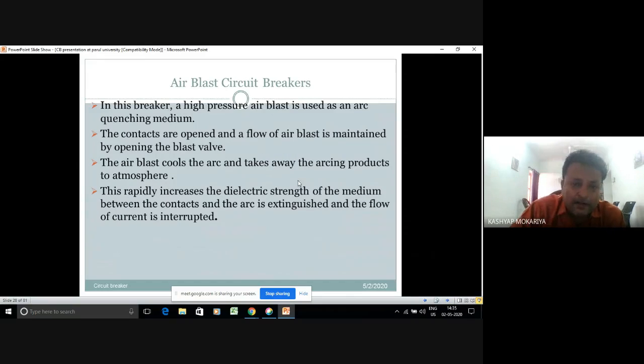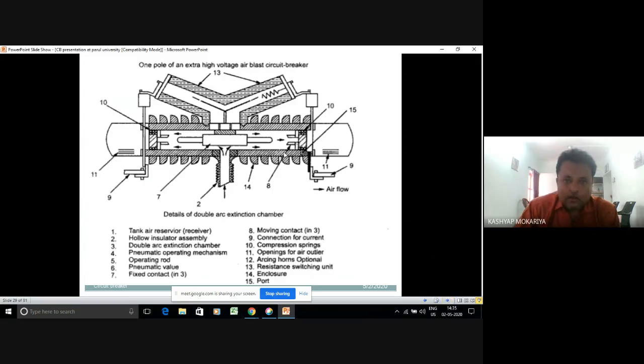Air blast circuit breaker. In this breaker, a high pressure air blast is used as the arc quenching medium. The contacts are opened and the flow of air blast is maintained by opening the blast valve. The air blast cools the arc and takes away the arcing products to the atmosphere. This rapidly increases the dielectric strength of the medium between the contacts, and the arc is extinguished and the flow of current is interrupted. So this is the assembly. This you can find in traction applications.